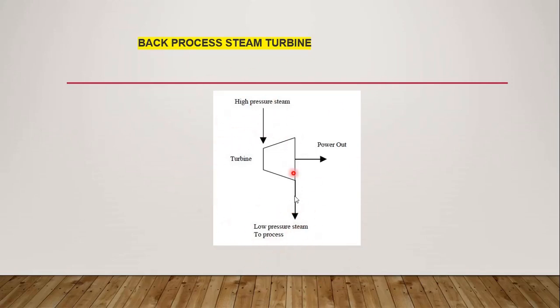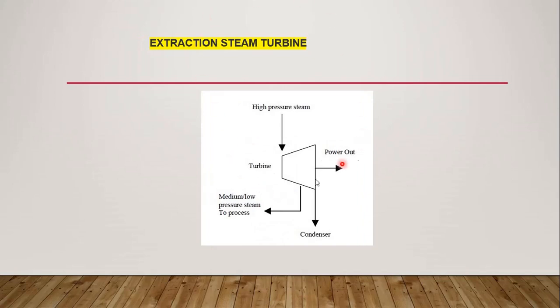The biggest disadvantage of this type of steam turbine is that it is highly inflexible. The output of this turbine cannot be regulated as it does not allow changing the pressure and temperature of the steam in the turbine. Whatever steam is coming in directly goes out — you can't regulate or control it. The thermal load of this turbine defines the flow of steam mass, which makes it difficult to change the output, and other methods to regulate output reduce the efficiency of the overall system.